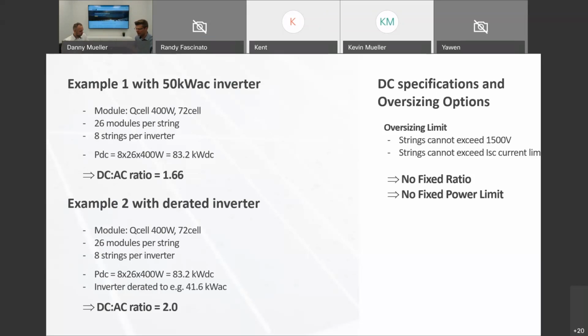If you want to go significantly above the 2:1 DC to AC ratio, you can not only scale the DC side of the system, but you can also scale the AC side of the inverter. We offer derating services: if you have a special contract, for example, 500 kilowatts AC, you are allowed to connect to your grid with your commercial customers, instead of 10 inverters, you can use 12 inverters. And if you do the math, if you derate every single inverter to about 41.6 kilowatts, you will still maintain the 500 kilowatt contract capacity, but at the same time, by reducing the AC capacity, your DC to AC ratio will increase over that limit we had before.